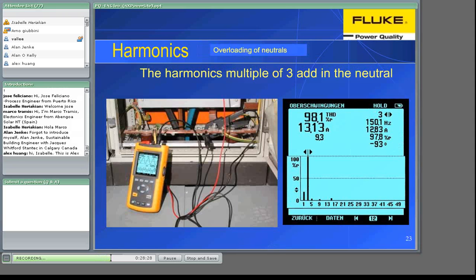When phase currents consist of the fundamental current only, the summation is zero. If the phase conductor contains both fundamental and triple harmonics, the result is different. Triplen currents, as we said, will add in the neutral conductor. We are faced with overheated neutrals. This picture shows a network analyzer measuring a third harmonic in the neutral, where you see the value is over 97% of the RMS value, a very high content.